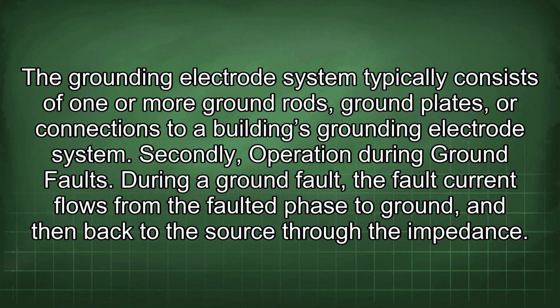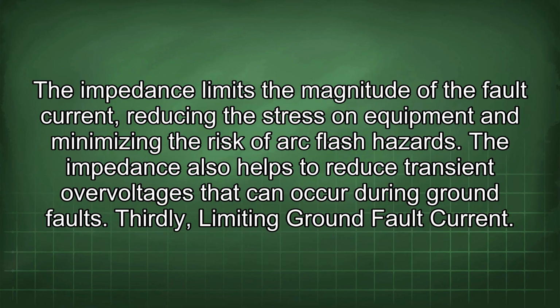During a ground fault, the fault current flows from the faulted phase to ground, and then back to the source through the impedance. The impedance limits the magnitude of the fault current, reducing the stress on equipment and minimizing the risk of arc flash hazards. The impedance also helps to reduce transient overvoltages that can occur during ground faults.